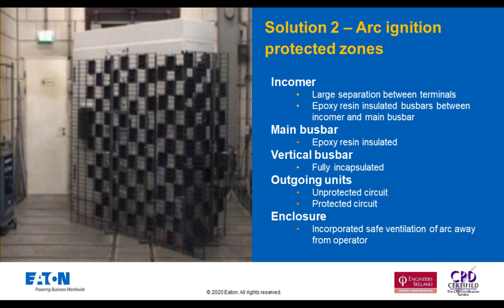And then finally, you've got Class I, so this is an insulated assembly, and this assembly provides reduced risk of arc faults solely by means of arc ignition protected zones. So the likelihood of an arc happening within the assembly is very limited, due to insulation of lines and the remote possibility of arcs happening.